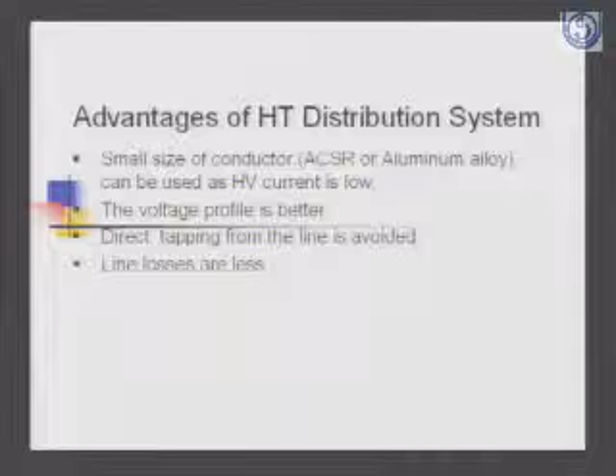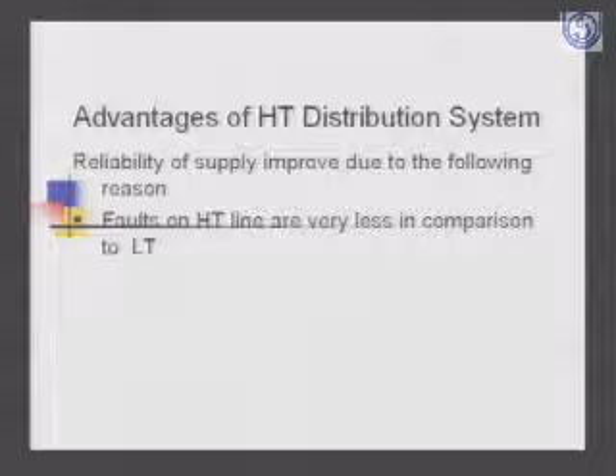Reliability of supply improves. Generally the system fails because there is an LT fault, and when the LT itself is reduced, then reliability is improved. And further, whenever a transformer fails, it's only those 3-4 consumers who are connected to that transformer which are affected, and not a large number of consumers, as in the case of, say, a 630 kVA or a 1000 kVA transformer, where a large number of consumers are connected to one transformer.